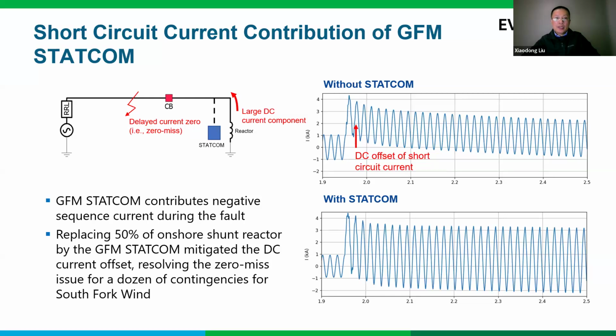However, as shown in the diagram, when there's a fault either on the grid side or on the export cable side, the fault current has a larger DC component, which makes the fault current miss the current zeros for many cycles, as in the example here. So the breaker cannot interrupt the fault, cannot open, right, after 4 or 5 cycles. So this will result in breaker failure, right? The zero miss issue is the worst when the export cable is energized into a fault. The issue must be resolved in order to safely energize the offshore wind farm.